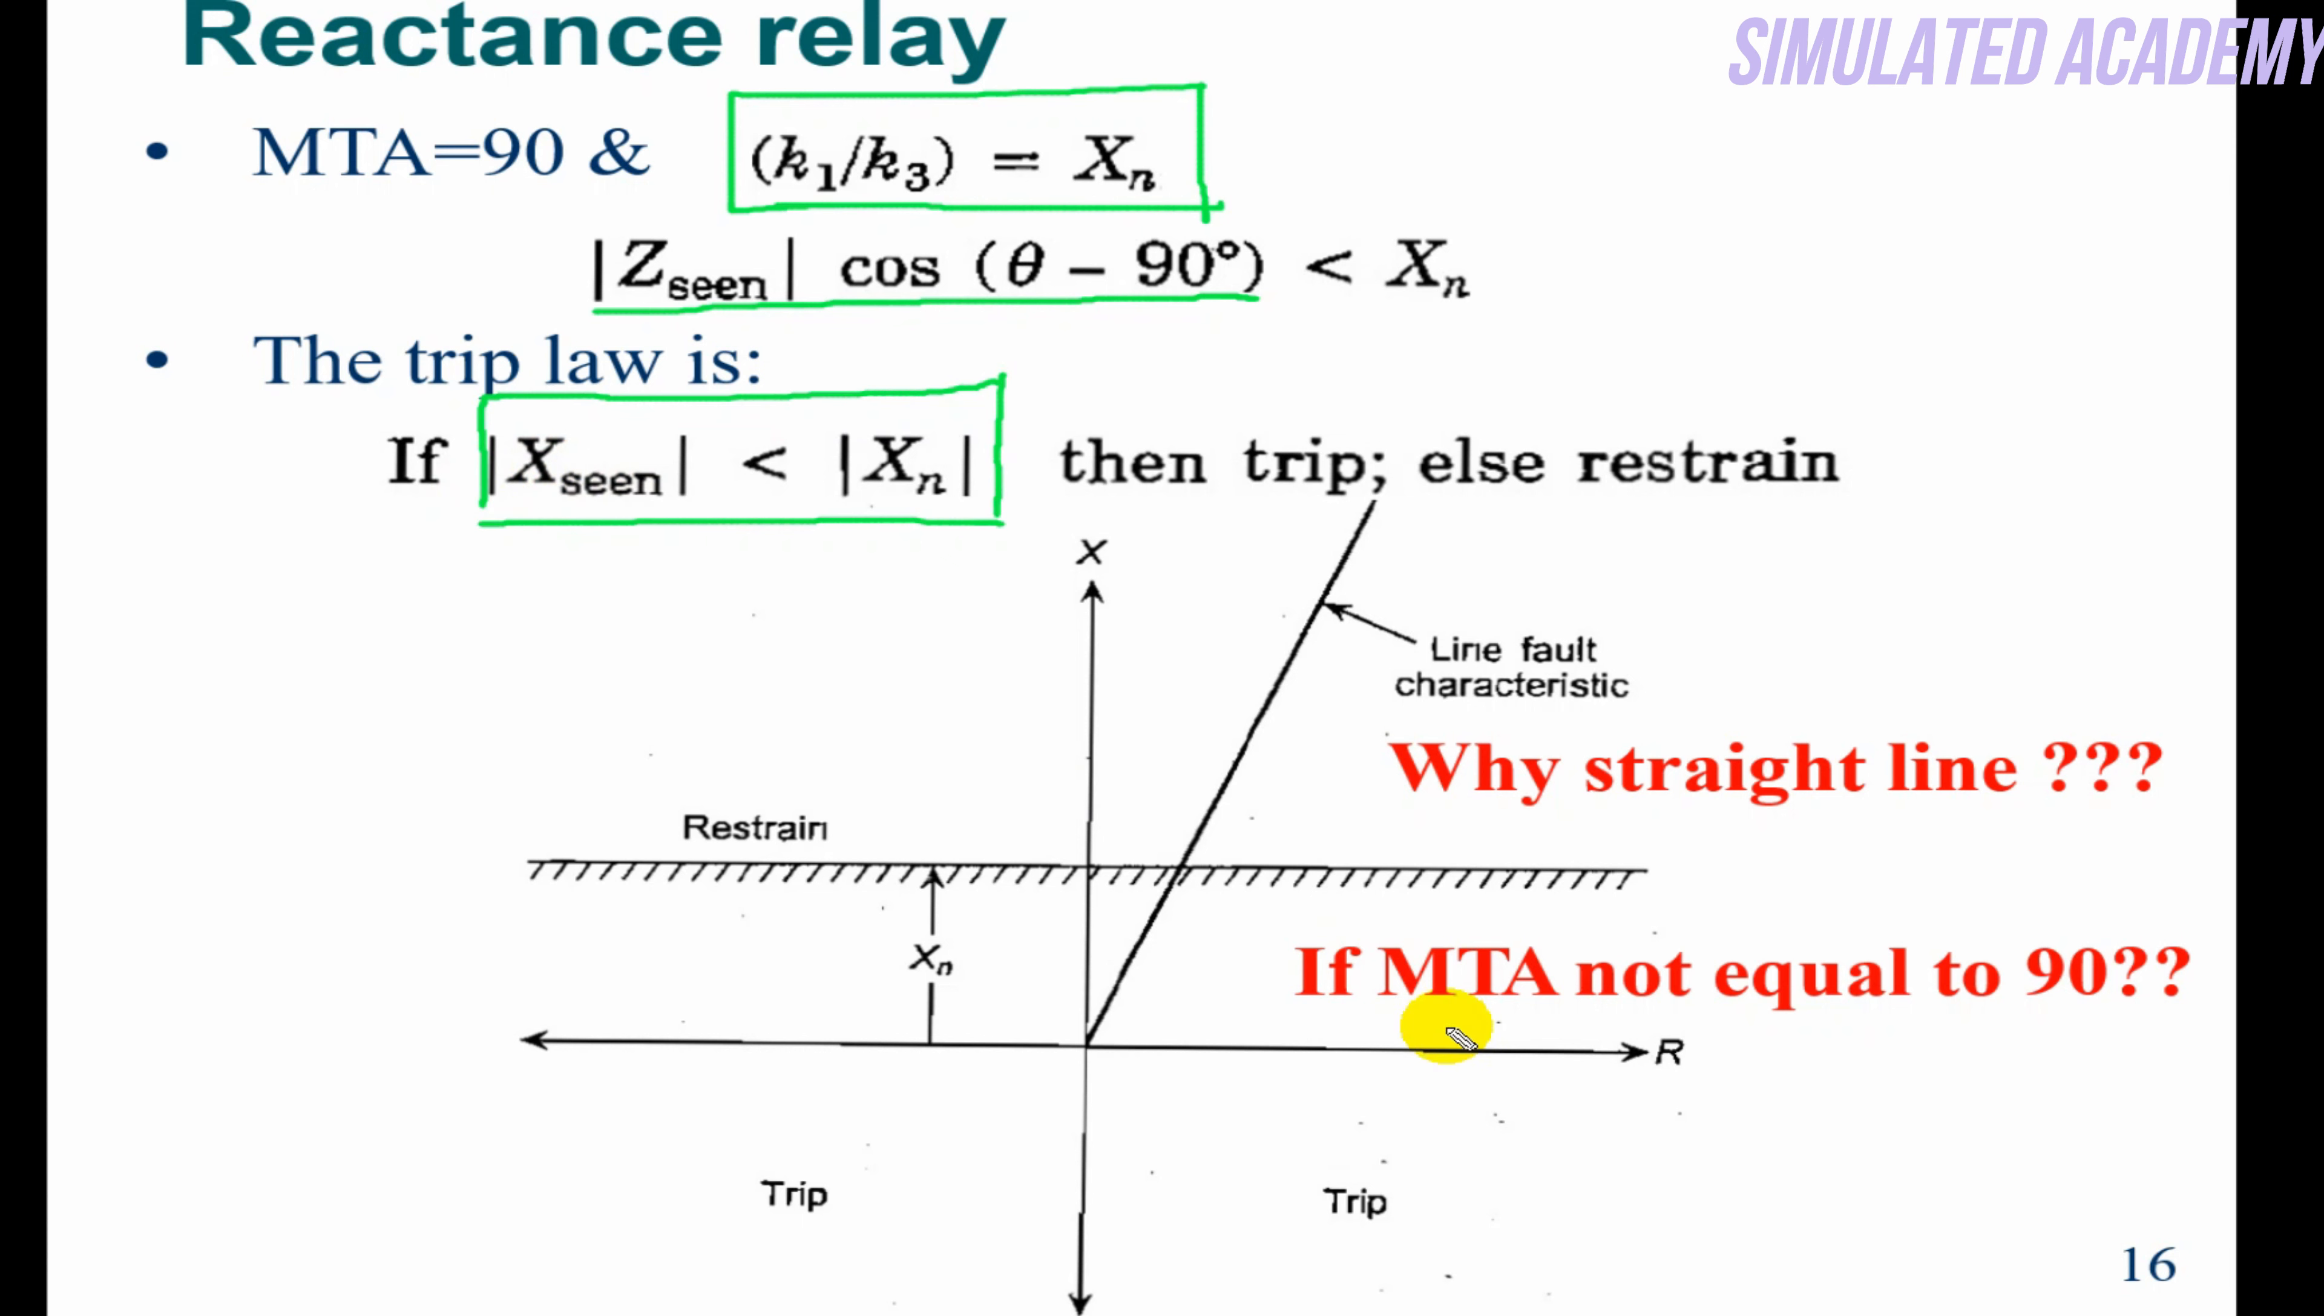So how will you plot this in an X-R graph? On the X axis we have R, and on the Y axis we have X reactance. So this is what we're getting: this straight line. Below this, if X_n value comes, it will trip; otherwise it will restrain on the upper side.